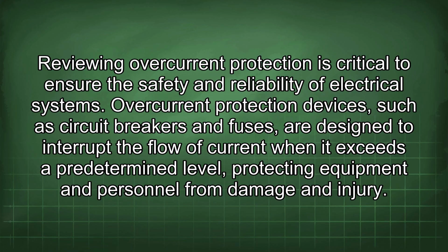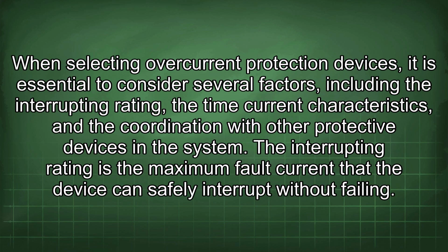Overcurrent protection devices, such as circuit breakers and fuses, are designed to interrupt the flow of current when it exceeds a predetermined level, protecting equipment and personnel from damage and injury. When selecting overcurrent protection devices, it is essential to consider several factors, including the interrupting rating, the time current characteristics, and the coordination with other protective devices in the system.